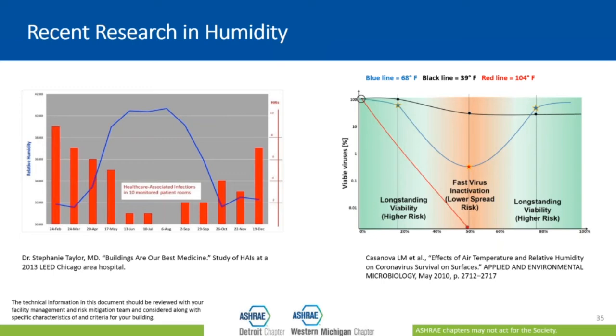They looked at 10 patient rooms and studied them for about 13 months. They had over 8 million data points, and 400 patients went through those rooms. They looked at the patients' incidence of hospital-acquired infections as building performance metrics varied in those spaces. And what they found was that, sure enough, when the relative humidity was low, you saw more infections. When the relative humidity was higher, when it gets up into that 40% range, the number of infections goes down. In some cases, on a couple of days, it was even down to 0.